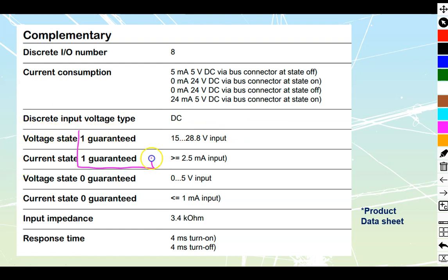What we do want to take a look at is these ones over here. The voltage state 1 guaranteed and current state 1, and the voltage state 0 or the current state 0 guarantee that we are going to have. And what this tells us is acceptable limits for use. If we take a look, we have got 24 volts nominal input. In reality, this thing is going to take anything that is from 15 to 28.8 volts. So anywhere in this range is considered to be a good high input or what we would refer to as a 1.